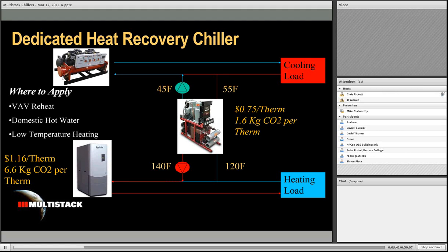So what we have here on the top of this slide is a chiller, and the diagram represents the cooling load, and on the bottom, the heating load. And a dedicated heat recovery chiller essentially straddles those two in a side stream parallel arrangement. So we take 55-degree chilled water from the cooling load. We take a little bit of that, we chill it, we pass it back to the prime mover, the main chiller, and then we take the heat from that water, combine it with heat of compression from the compressors, and we pass it off.